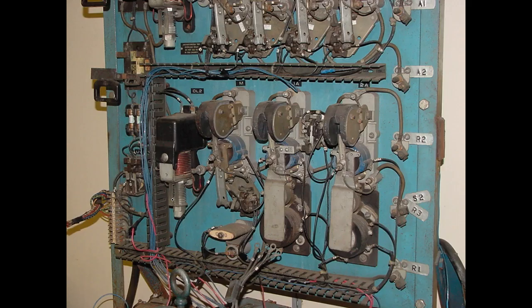This is actually a panel that we used to have. It's the DC panel, high voltage DC panel. And you can actually see the blowout, the actual paddle that's coming up from the blowout coil. You can't see the blowout coils themselves because they're in here. So the coils themselves are right there. We used to have this panel here. U.S. Steel used to send their electricians out here to troubleshoot. And we would bug this panel, and these guys would have to figure out what was wrong with it. That was part of their test. And what happened to the panel, I don't know. But... So, blowout coil.